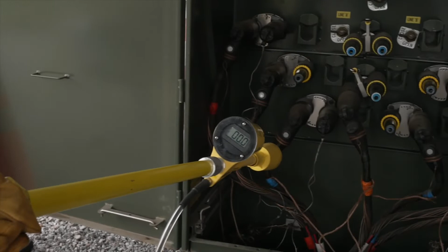So remember, when you high pot and want to de-energize that cable you high potted, watch however long it took to high pot with, and watch your tool bleed that high potted cable off, maybe through the feed, to ground. You're going to watch your tool tell you it's de-energized. It takes about the same amount of time, depending on the voltage and the length of that source. Add a few extra seconds just to be extra sure, and add a little more time in your mind.